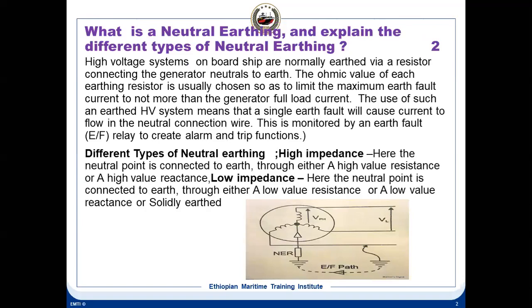What are the types of neutral earthing systems? Neutral earth system means the neutral of the generator is grounded through an NER. The whole purpose of the NER is to limit the fault current, and the NER value has to be such that the limiting current should not be more than the generator full load current. That means the fault current flowing in this should not exceed the generator full load current. So generally it is used on high voltage ships, and like you see in this case, there will be a leakage current, but these neutral earth systems are not allowed in tanker ships.